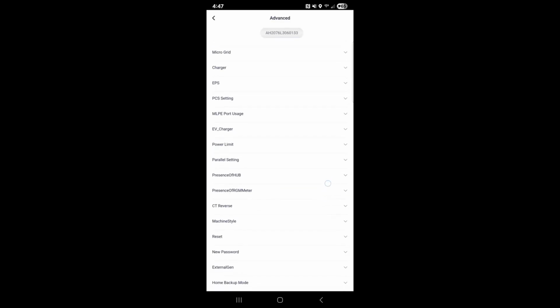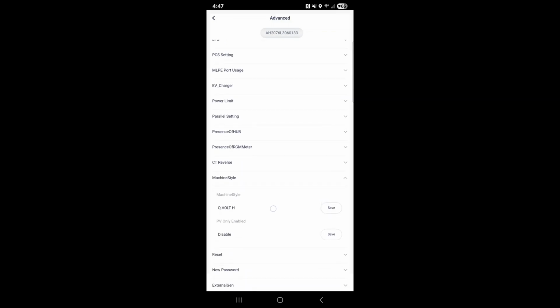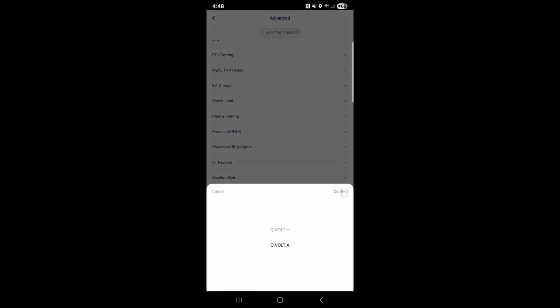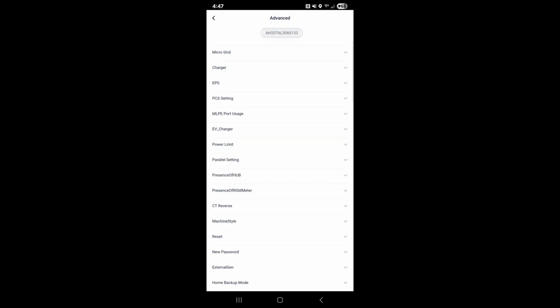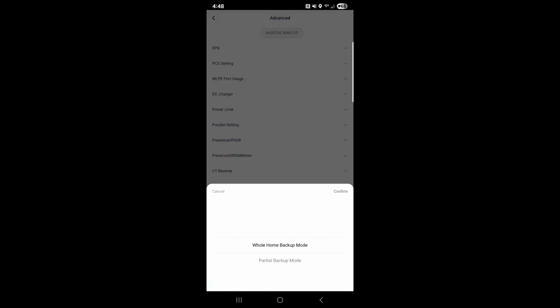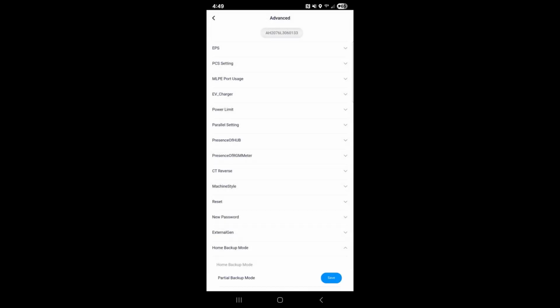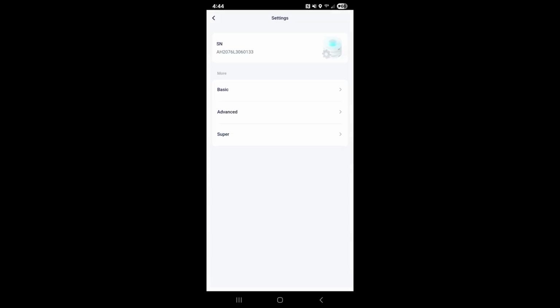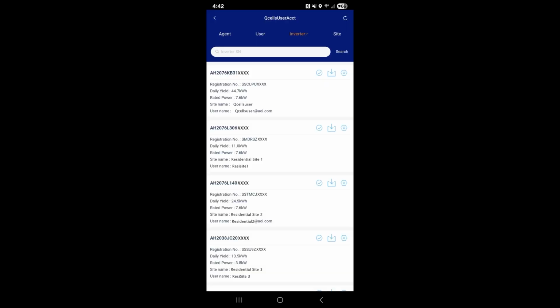Scroll down the list to verify the machine style is set to Q.VOLT H, and press Save. Scroll further down and select Home Backup Mode, then select between Whole Home or Partial Home Backup. Once complete, exit out of the inverter settings and go back to the inverter list to complete the next step.